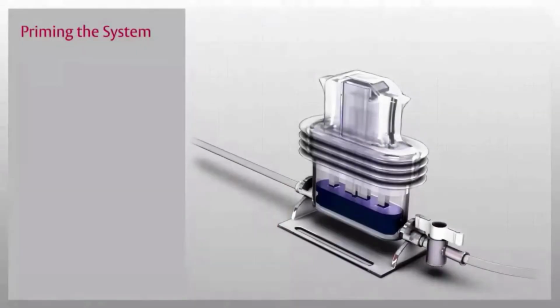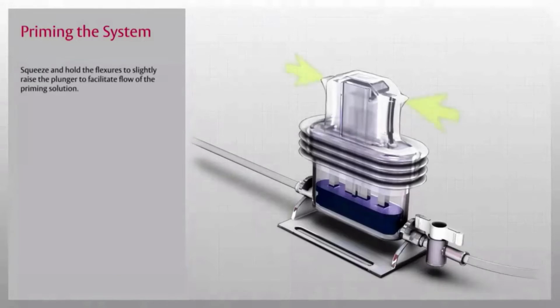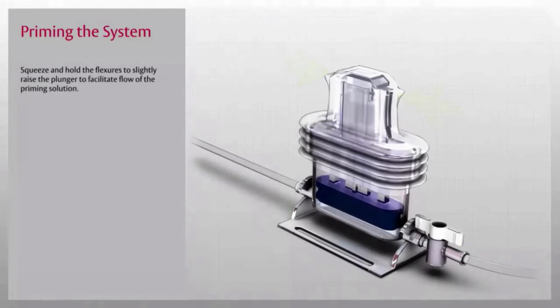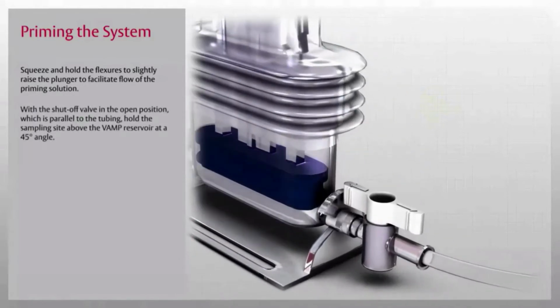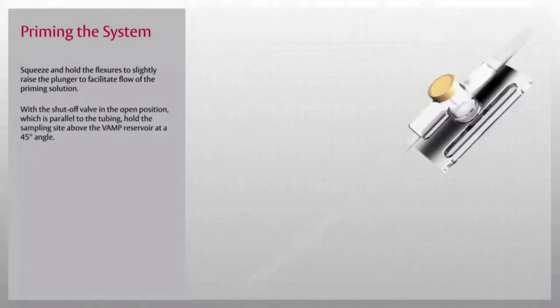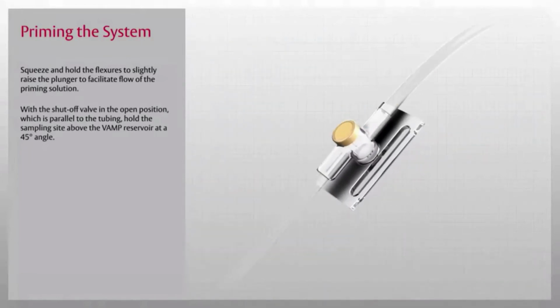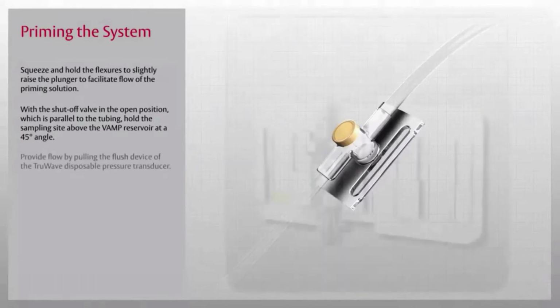Now that you have set up the VAMP Adult system, let's learn how to prepare and use the system. The first step is priming. To begin, first squeeze and hold the flexures to slightly raise the plunger to facilitate flow of the priming solution. Now, with the shutoff valve in the open position, which is parallel to the tubing, hold the sampling site above the VAMP reservoir at a 45-degree angle.